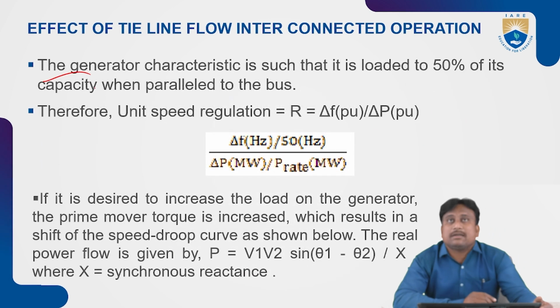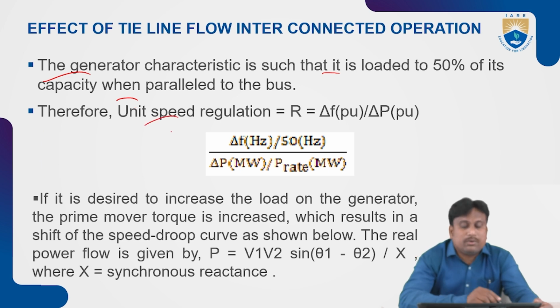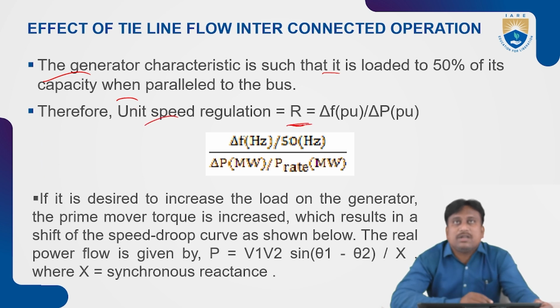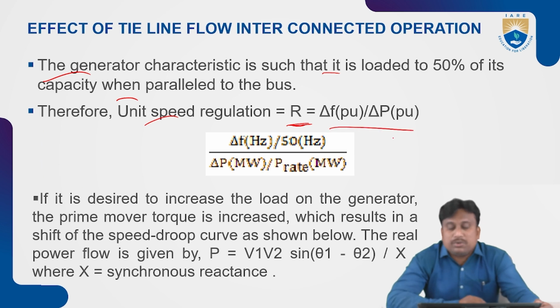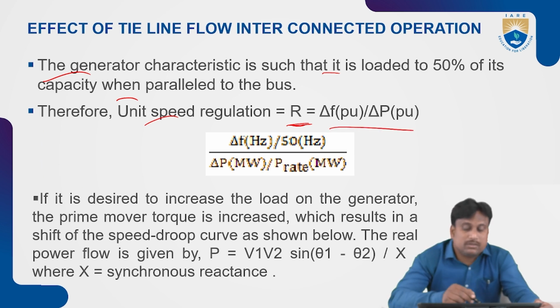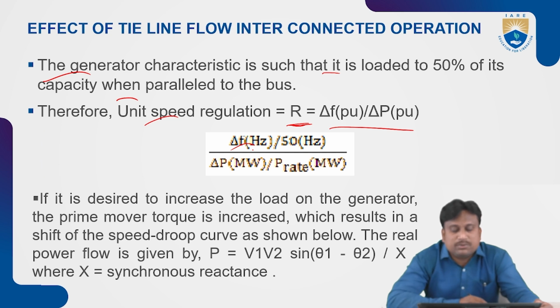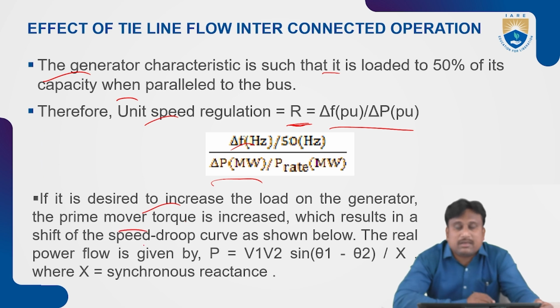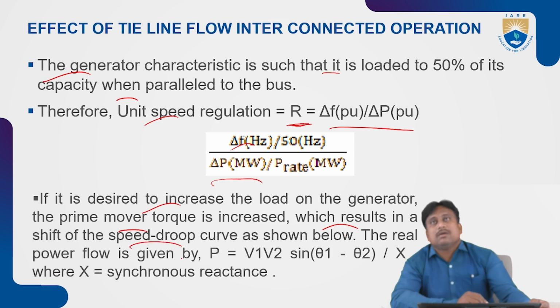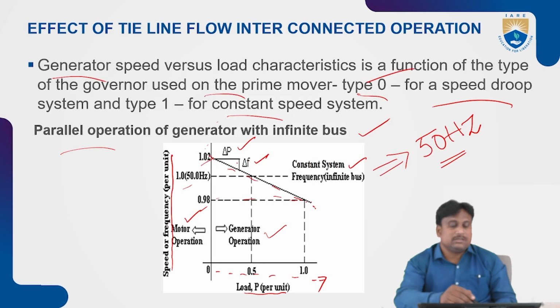Generator characteristics are such that it is loaded up to 50% of its capacity when it is supposed to be parallel to the bus. Therefore, unit speed regulation may be achieved as delta F in per unit to delta P in per unit. So delta F in hertz by 50 Hz is the numerator, and the denominator is delta P in megawatts by rated power in megawatts. If it is desired to increase the load on the generator, then the prime mover torque is raised, which results in shifting of the speed droop curve that we already discussed here. This is the drooping of the curve.